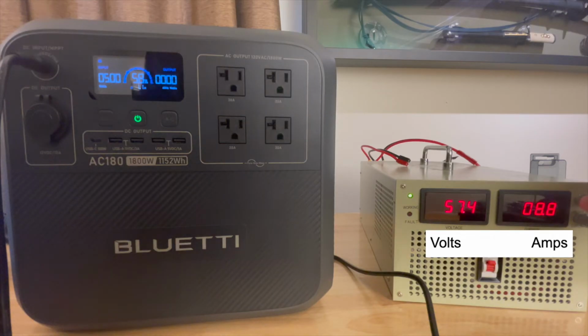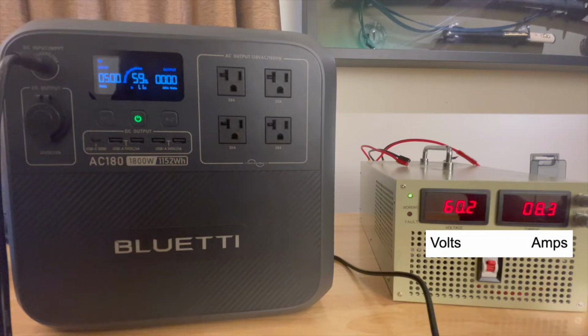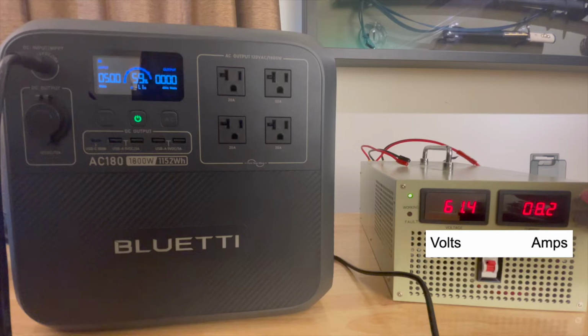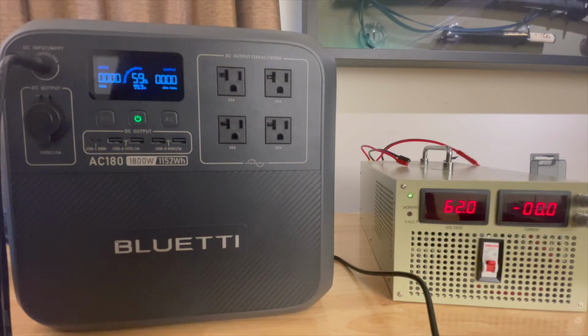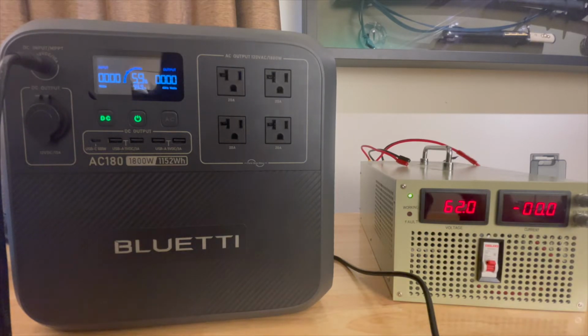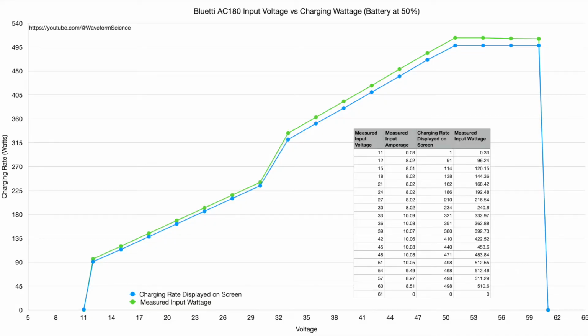So you have this nice easy area here, and 60 volts is the rated maximum — we're still pulling power here. However, once we get to about 62 volts, it zeroes out. When I tested it earlier, it actually zeroed out at 61. So here's what I tested earlier: you can see this bump right around 30 volts — that's where it decides to start pulling full current.